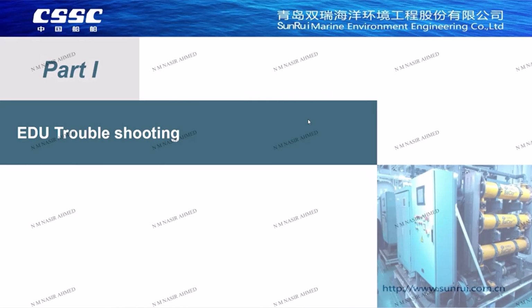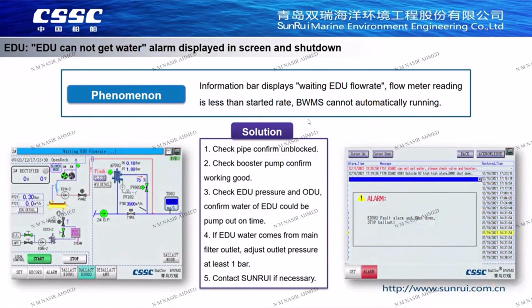First part, EDU troubleshooting. The first one is EDU cannot get water alarm. It may appear when the system is just started. On the top of the screen, the message bar will always display wait for EDU flow, and the value of EDU flow meter is always lower than the system startup flow.